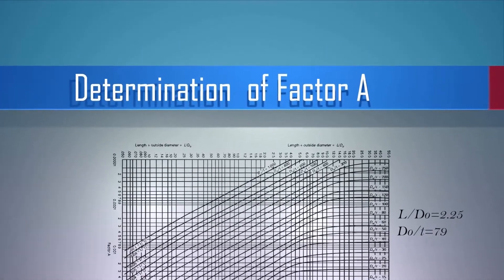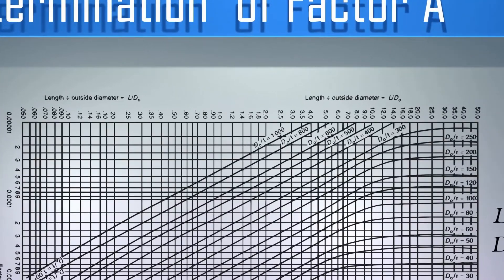Here is the geometric chart for components under external and compressive loading for all types of materials. L by D0 is 2.25 and D0 by T is 79, taken from the previous example. And here is the axis for L by D0.